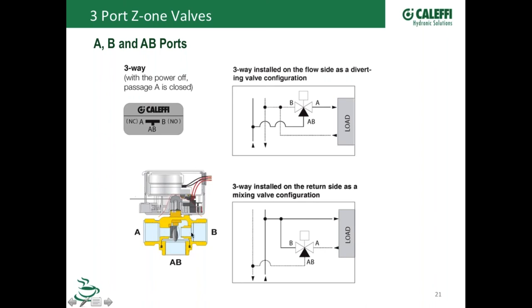And when you say repipe it, really all you do is take it out and flip it over. I mean, that's the pipe change, is just take it and rotate it 180 degrees. You don't have to go in and cut all the piping out of the building and start over. Just take the valve, rotate it 180 degrees and sweat it back in, or if you have our tailpieces, just unthread it.